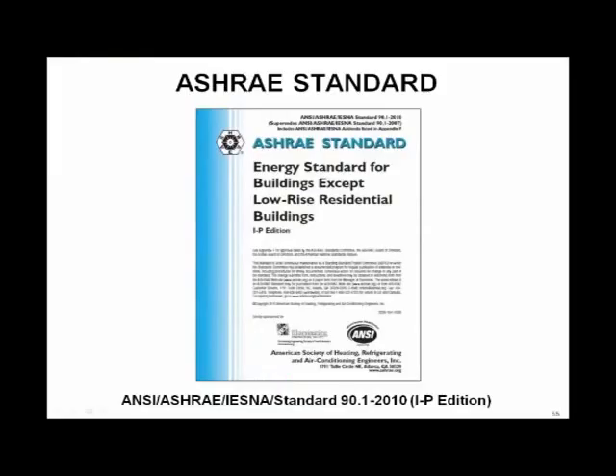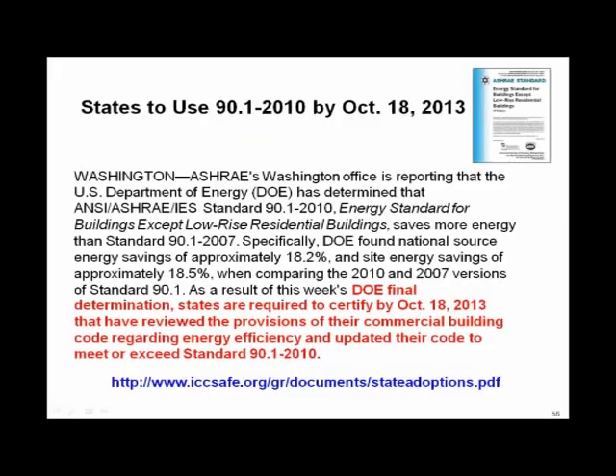So, ASHRAE standards, what are we looking at? 90.1 2010 is the standard I like to refer to real quick and examine a little bit of how it is impacting condenser water piping, and what should engineers know about that, and what are the changes being caused by this. By the way, 90.1 2010 is out, and that's the one everybody's talking about. 2013 is also out. It has not been ruled on by DOE yet, but it eventually probably will be. But let's take a look at 90.1 2010.